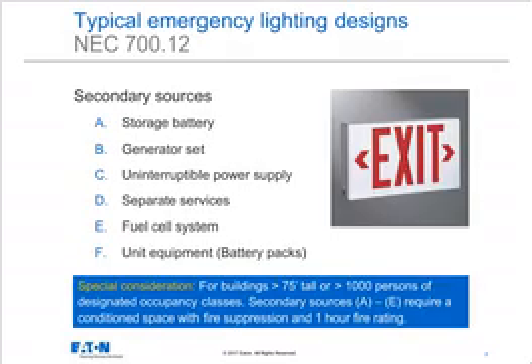So looking at NEC 700.12, the typical emergency lighting designs, there are several ways to do this. I can use a simple storage battery that I recharge and run my emergency lighting off of DC power from that battery. That's relatively uncommon except in large battery-intensive facilities like telephone central offices, for example. A generator set is much more common, and again, if the generator can start and stabilize quickly, it can be the source for emergency lighting backup. The UPSs are uninterruptible power supplies that we'll be talking about in this presentation.